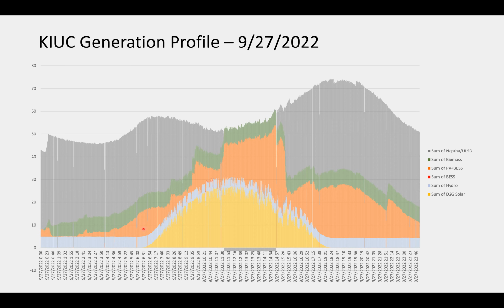In orange, or this kind of pinkish color, this is actually the solar PV coupled with battery that we do set point dispatch throughout the day, as long as we have the state of charge to do that. And so you'll see here, even though the solar day starts, you don't really see a lot of that energy until midday and later on during our evening peak, which is when we really try to drive down our need for requiring more diesel generation to turn on.